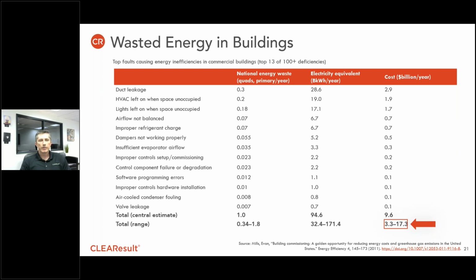There were over 100 deficiencies identified across these commissioning projects. He pulled together the top 13 and tried to put a number on the energy waste happening and what that would cost, estimating somewhere between $3 and $17 billion a year across the US going to energy that was completely wasted. Not energy helping a customer feel comfortable or a building perform better, but energy wasted through leakage, airflow not being balanced, dampers not working properly, and other things shown on this chart.